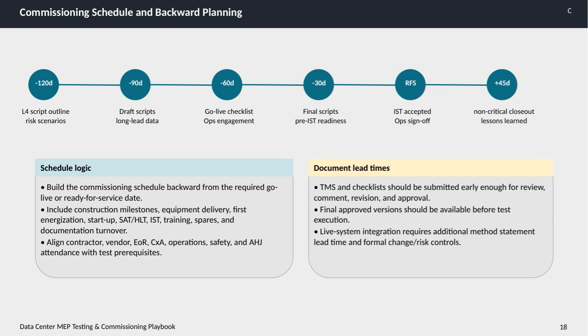Test method statements and checklists need to be submitted early to allow sufficient time for review, comments, revisions, and final approval. The approved documents must be available before starting any test execution. For live system integration, additional lead time is required for method statements, along with formal controls for any changes or risks, ensuring everything is carefully managed and compliant. Overall, this backward planning approach keeps the commissioning process organized, efficient, and aligned across all parties, minimizing surprises, and ensuring the data center is ready and operating smoothly by the required deadline.